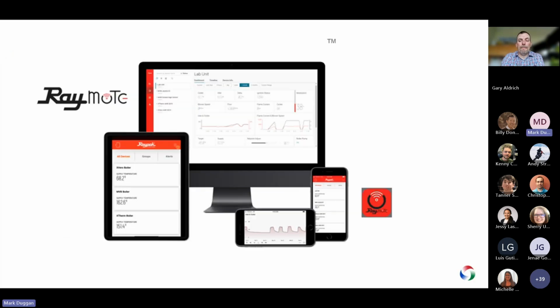We also offer Raymote. This is on the XVers core, but it's on any boiler that has our Versa control platform, which is basically all of our boilers at this point. With Raymote, you can download an app on your phone, or if you don't want to do that, you can create an account on your desktop. If you have a building owner or maintenance group that has several different boilers, or even one boiler, that they don't want to have to go into the boiler room to monitor, this allows remote monitoring. So you're able to see inlet temperature, outlet temperature, system temperature, run times, basically any parameter you could possibly think of on this boiler. You're able to view it remotely.